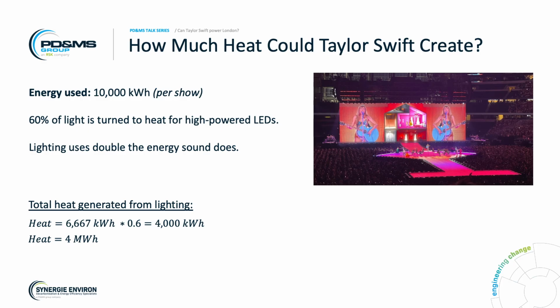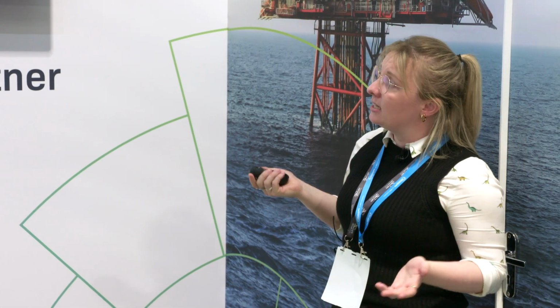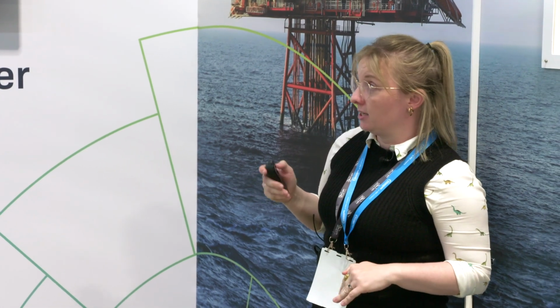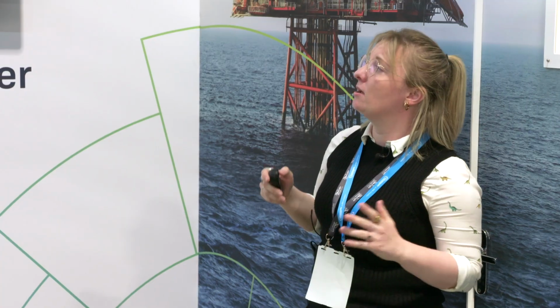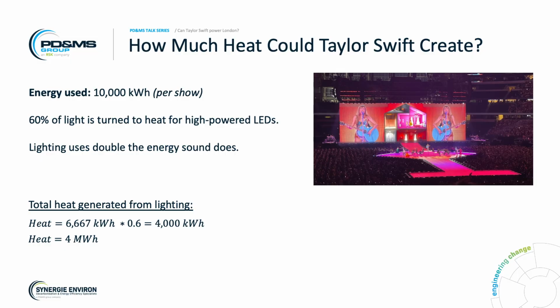So how much of that is being turned to heat? In lighting, 60% is turned to heat when you're using high-powered LEDs, and I'm making an assumption here that it's high-powered LEDs. Lighting also uses double the energy that sound does, so the total heat generated from lighting is double the amount from sound, which is 6,666.67, times the 60%, giving 4,000 kilowatt hours, or 4 megawatt hours of heat.